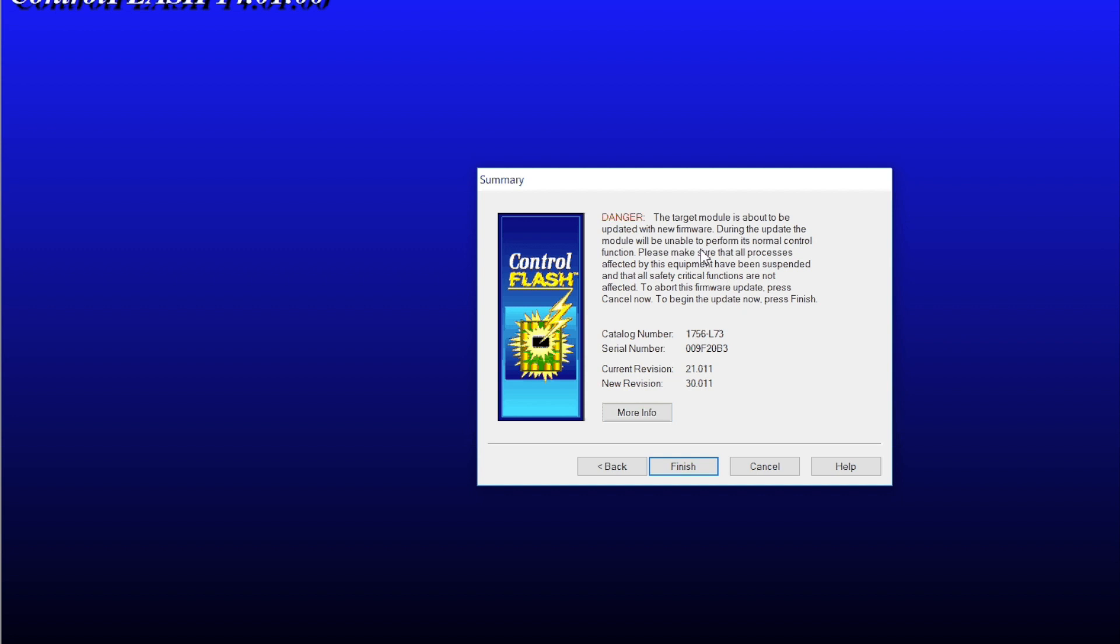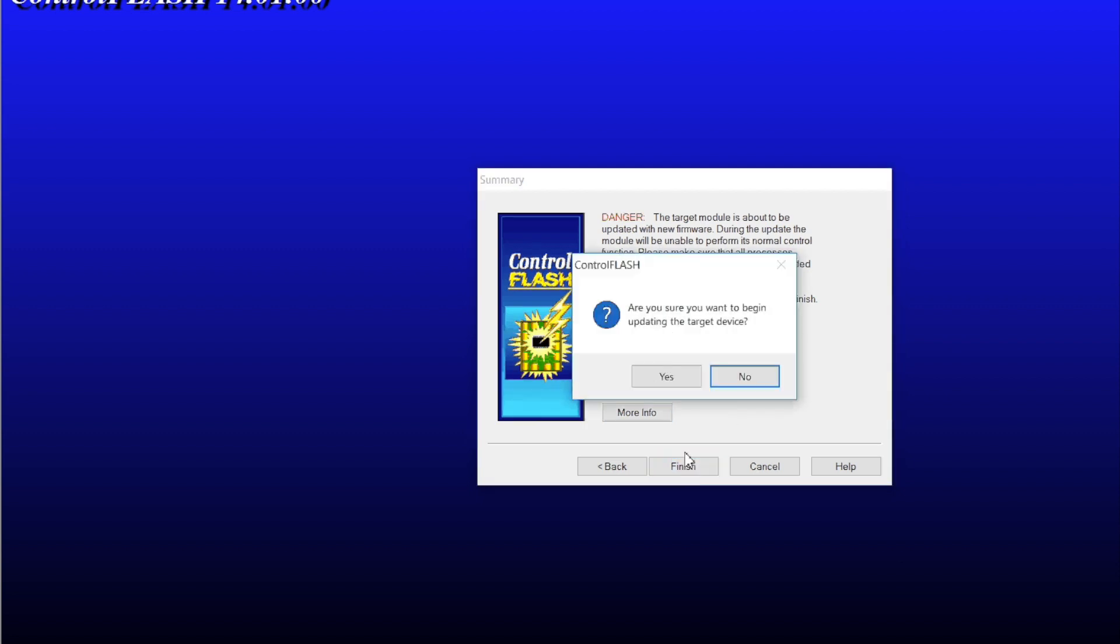It's going to give you a warning. And this is important. When you update firmware, it wipes out your processor, removes project in any and all configuration and settings. So be aware of that. Make a backup of your project file first. Clicking next, you're going to get one more time, one more chance to change your mind.